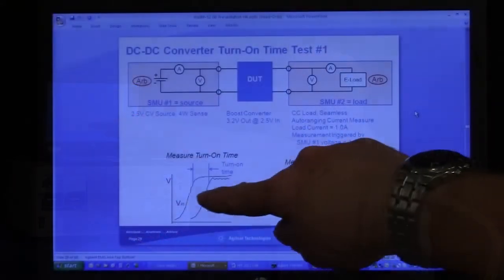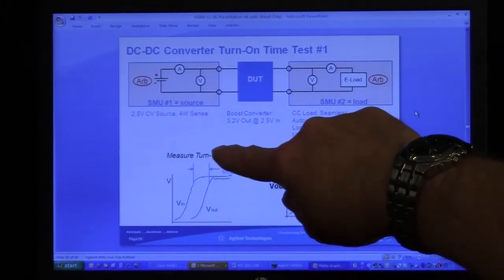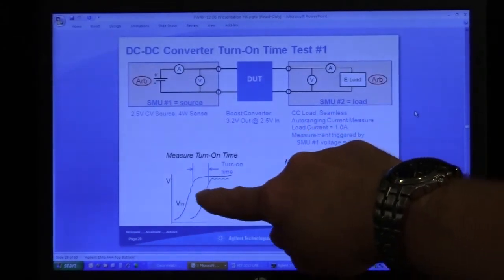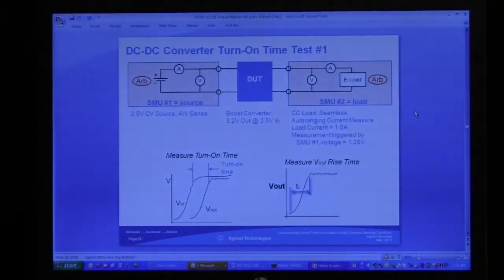Now the test that we're actually going to be doing is a turn on time test. So we're going to turn on the input side of the DC to DC converter and measure how long it takes for the power to come out of the DC to DC converter. And of course that startup time is a critical measurement for anyone who's doing DC to DC converter design, because the faster it starts up the more efficient it can be in its operation.